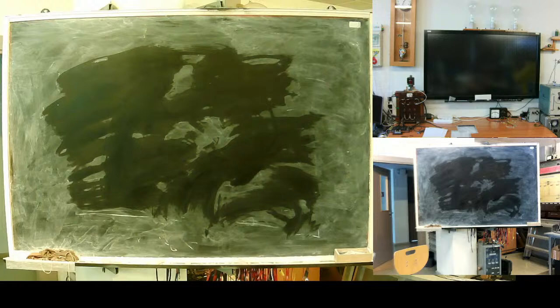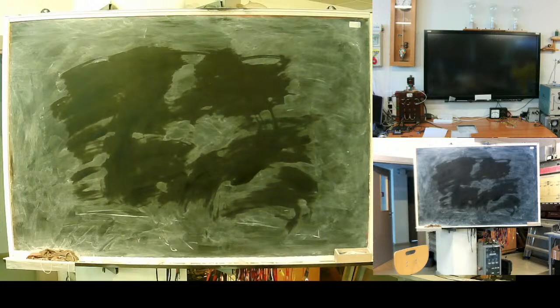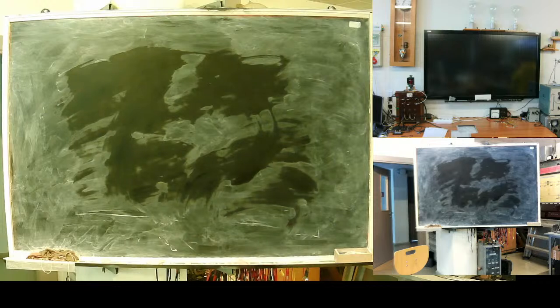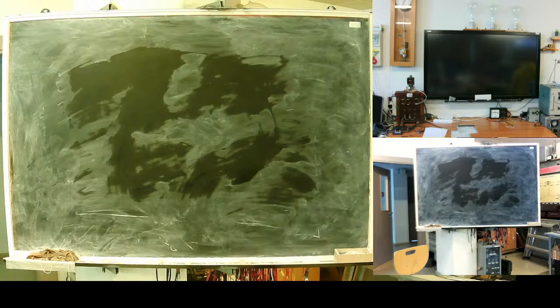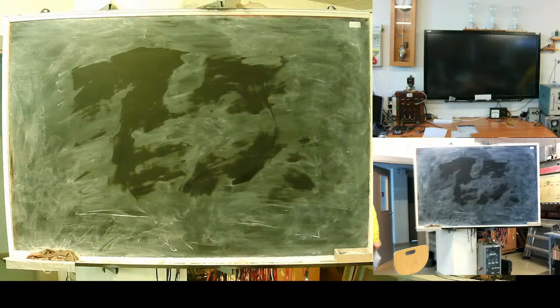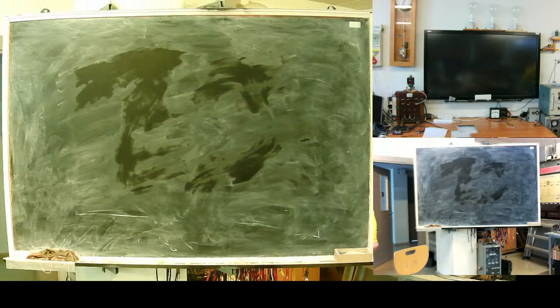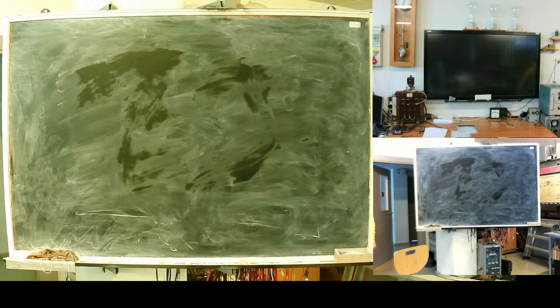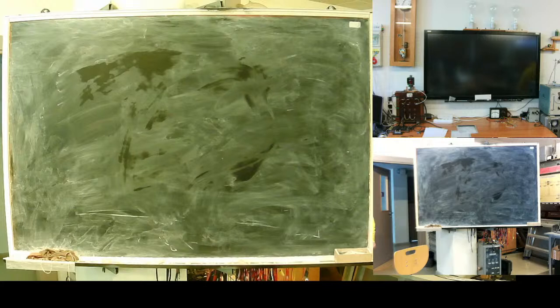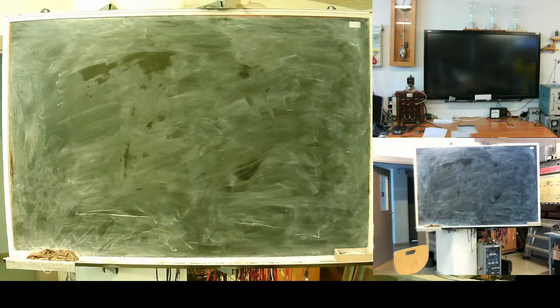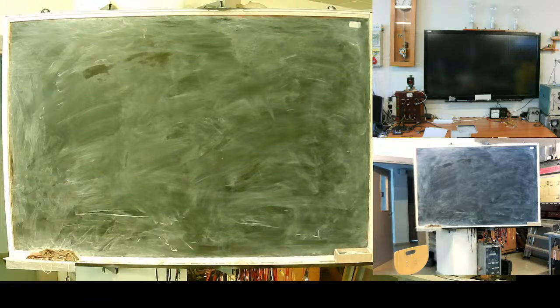In all this time, have you ever seen an American meter? With two current coils. It has one voltage coil and two current, even in single phase, because there are two voltages in a house: 110 for sockets and usual appliances, and 220 for the air conditioner, the washing machine, the water heater. Transformers with secondary winding have an earth point in the middle, and on two sides, one 110, one 110. If you use both, you will have 220. Sockets with two verticals, 110. Sockets with vertical and horizontal, 220.